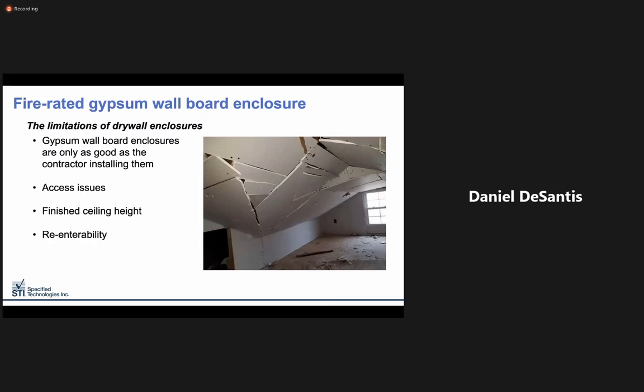Although drywall has been the go-to solution for fire-rated shaft containment, it does have its limitations. Access is the #1 issue when using drywall. This is especially important in the retrofit market segment, which we'll be discussing a little bit later. But can you frame the area that needs to be protected? Think of a busy corridor or a commercial use building, HVAC duct running next to IT wiring, next to chilled water lines. It gets extremely crowded up there. Now try to build a 4-sided drywall enclosure around a 1-inch conduit that lays on a trapeze hanger 2 inches away from a return air duct.